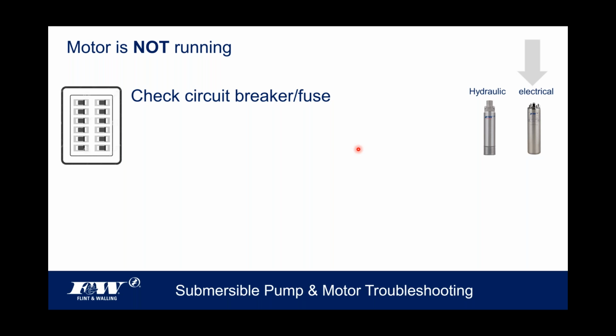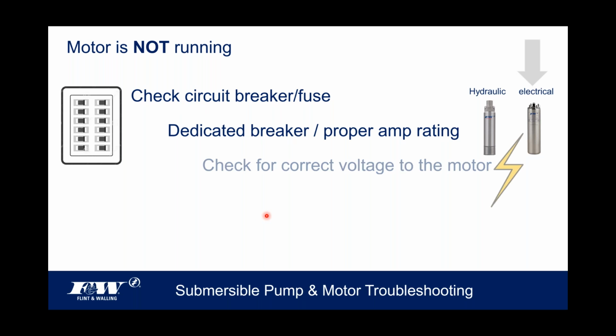Now, there may be a reason, and there probably is, for the fact that circuit breaker blew or that fuse blew. It's always recommended that you use a dedicated breaker for your well pump, just like you do an air conditioner or a range. A lot of these appliances will have dedicated breakers. It's also important that you put it on a breaker that has the amp rating to handle the amp load. If we cut corners on either of these, we could get nuisance tripping of the breaker. In fact, if you do get tripping of the breaker, and every time the pump fires up it blows the breaker, here's one thing to check.